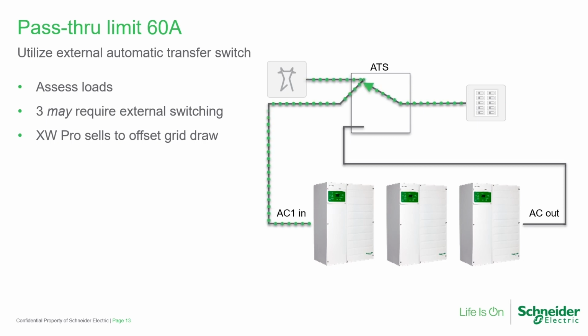Happily, we are now compatible with the WattNode meter offered by Continental Control Systems for zero export on XW Pro. So this will utilize an upstream CT that is placed between the meter and your feeder for the automatic transfer switch, and it will limit the sell power to zero out any power so it doesn't get pushed back to the grid.